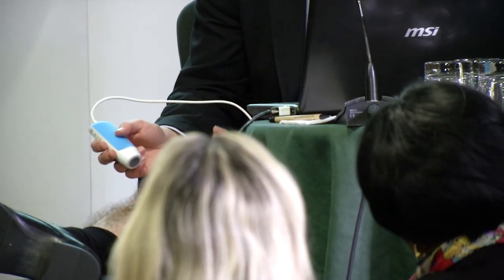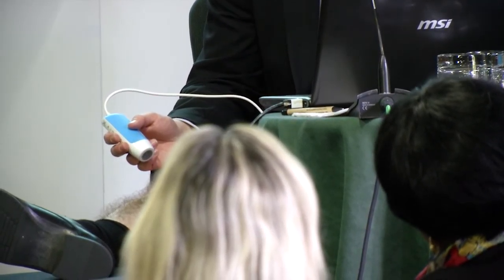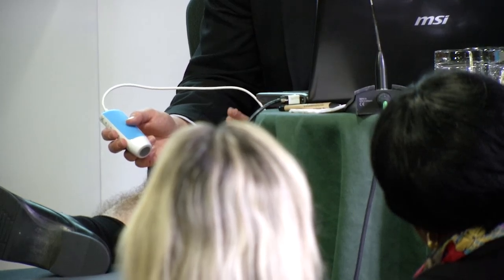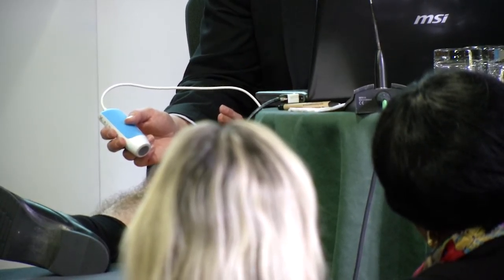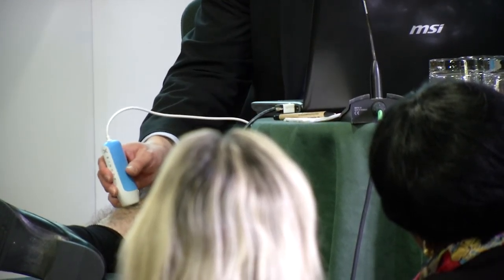Now we have connection to the computer, so we are on the same face. I calibrate the device, and now measuring is on. What I'm doing is moving the transducer over the bone, and when I see clearly those two echoes, I stop the movement, and the software accepts the signal.